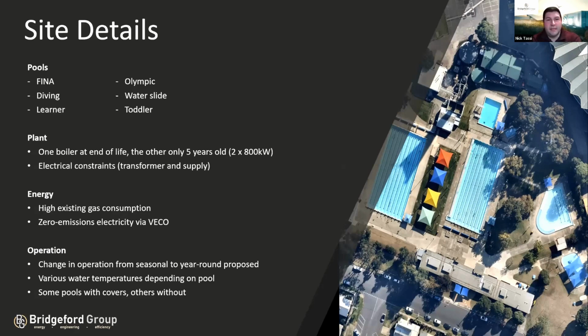The site has existing electrical constraints, which isn't uncommon for aquatic centres. I believe the transformers were around 500 kVA or 315 kVA, so that presents challenges for electrification, along with high existing gas consumption, being an outdoor facility. There's a requirement to ensure not only reduction in energy, but also providing the load that's needed. Geelong purchase their electricity from VECO, the Victorian Energy Collaboration, meaning it's zero emissions electricity, which presents a great opportunity to go from natural gas to electrified hot water.